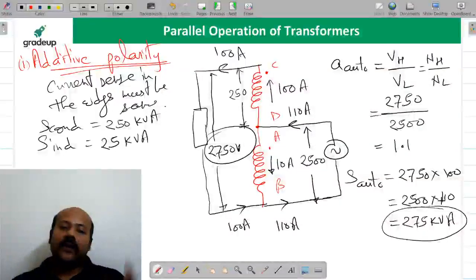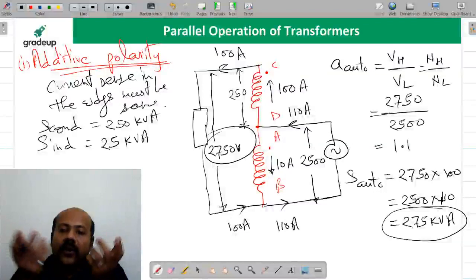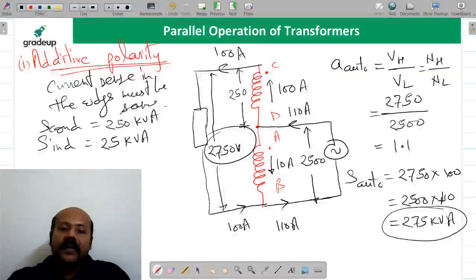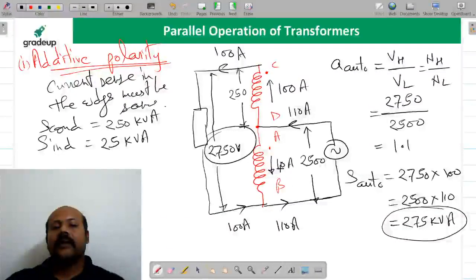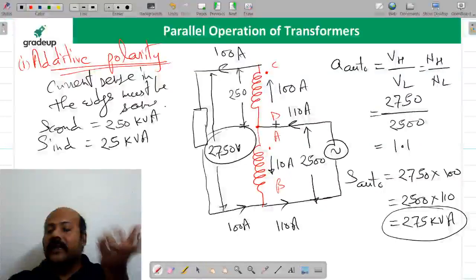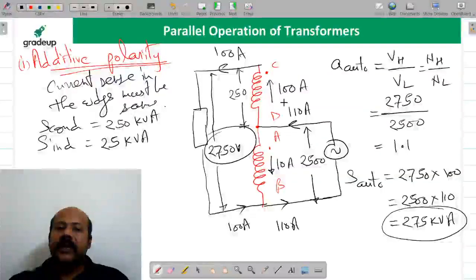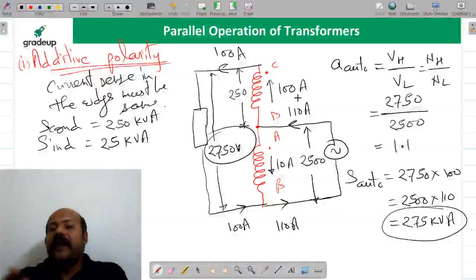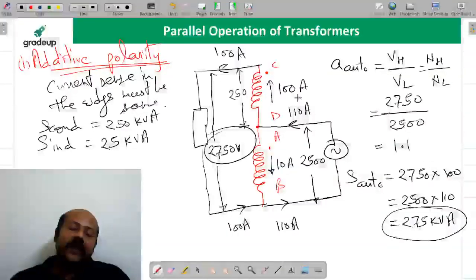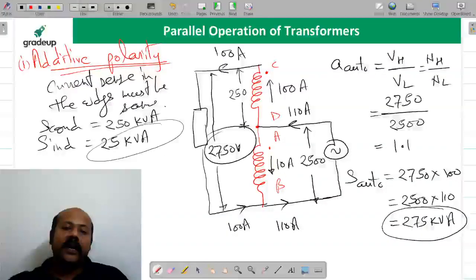I have already told you that your auto transformer is nothing but a two-winding transformer. What are the two windings? This winding CD and this winding AB. So these are the two windings of the previous two-winding transformer. So the inductively transformed VA is nothing but the rating of the previous two-winding transformer, that is 25 kVA. Directly you can observe it.